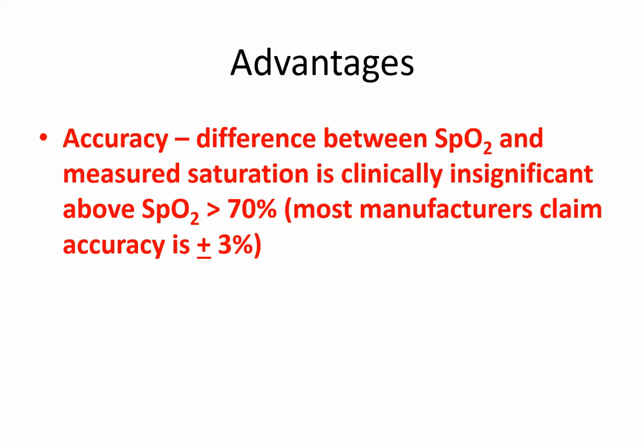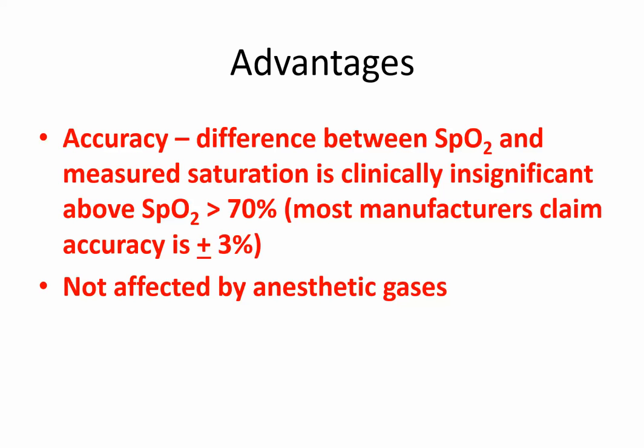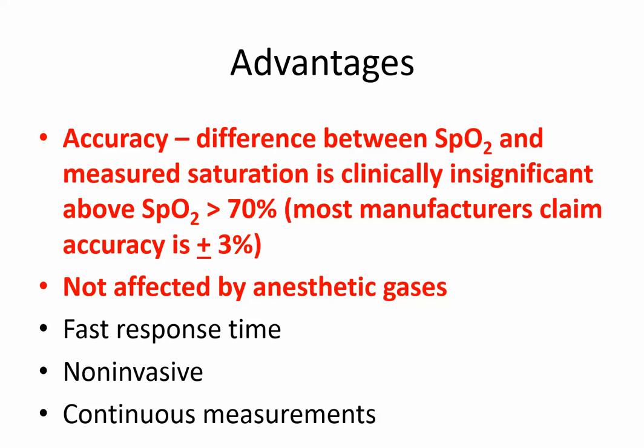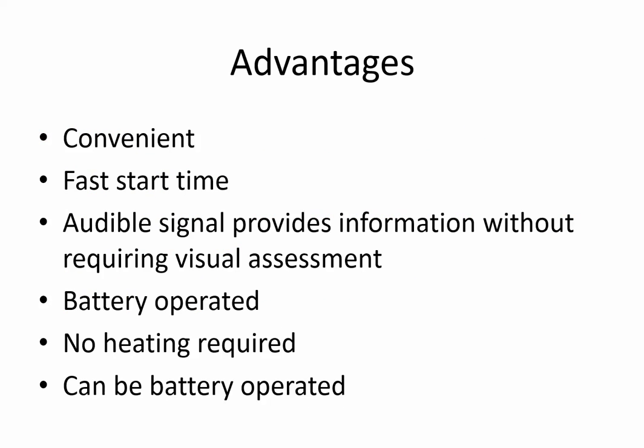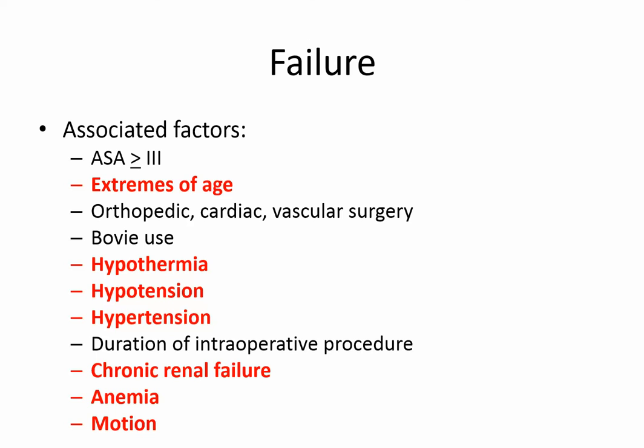The advantages of pulse oximetry. The difference between the measured pulse oximeter saturation and the measured saturation is clinically insignificant at saturations greater than 70%. It's not affected by anesthetic gases. I see that as a question on the test. Obviously, you know that it's got a fast response time, it's non-invasive, and it provides continuous measurements. It's convenient. The audible signal provides information without requiring visual assessment. You can use it in a battery-operated mode, and it doesn't require heating.